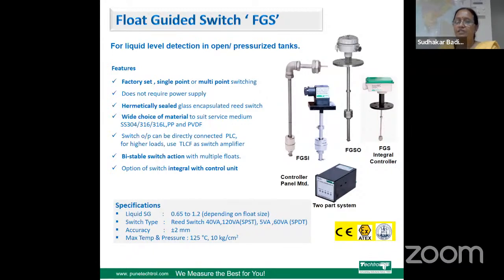Then bistable switching action is also possible with multiple floats. And the option of level switch with integral or remote control unit is also available. On the right side, you can see various types of level switches. This is a float switch, which is side mounted. Then this is with a plug-in connector. Then this is with the enclosure. And this switch is with integral controller. And this is a switch amplifier or level controller, which is used along with this switch as a two-part system.